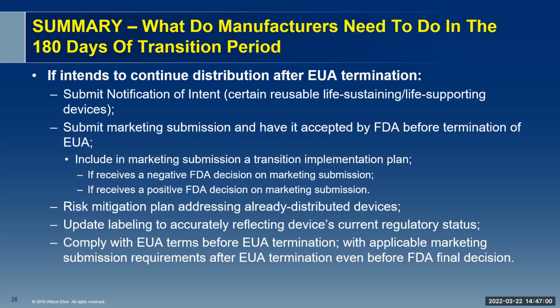In the marketing submission, you need to include a transition implementation plan to address what you plan to do to deal with the potential risks if you receive a negative decision from the FDA, and also what you need to do if you receive a positive decision from the FDA. You also need to have a risk mitigation plan, and you need to include that plan in your notification of intent if the FDA so requires. But either way, you need to keep that plan on file in case the FDA needs you to explain how you plan on mitigating the risks of your already distributed devices.